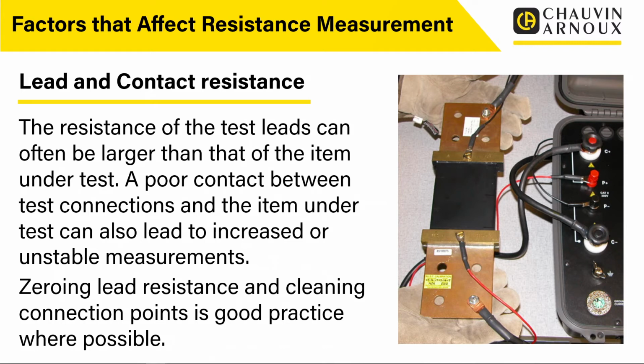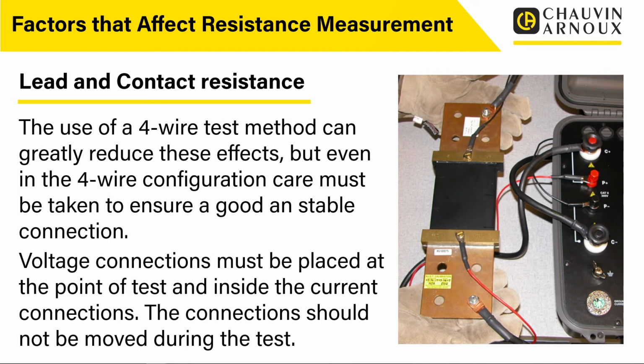Now, there are options. Zeroing lead resistance and cleaning connection points are always good practice where possible. This is specifically true for 2-wire measurements, but for 4-wire measurements, it is still good practice where we can to have good, clean, reliable test contacts. So the use of a 4-wire test method can greatly reduce these effects, but even with the 4-wire configuration, care must be taken to ensure a good and stable connection. That word stable is very important. You don't want it to be moving about, or changing during the measurement.